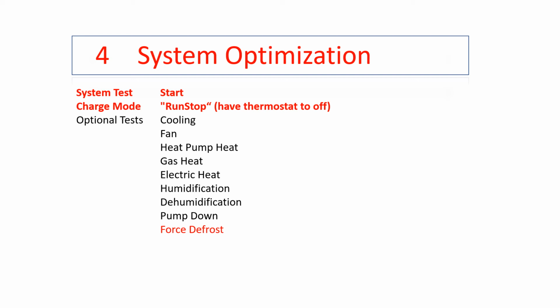So if you're on, let's say, a real estate inspection and it's 50 outside and you do not have a coil under 32, and you can check that under status, and we'll look at that in a moment. You can force the defrost, but it's not going to go into defrost because you're not under 32 degrees. All you do with forced defrost is accelerate the time.